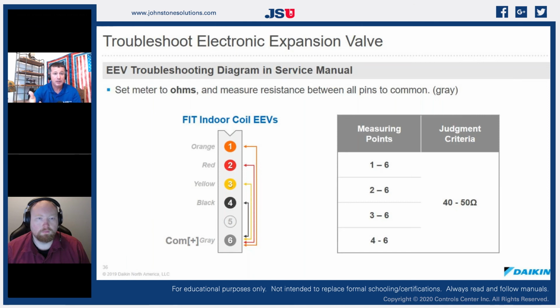When you fire up one of these units, you're going to hear that EEV opening and closing, and that's all it's doing, it's just firing at those individual windings, trying to open that thing up. Moving some of these expansion valves will run a couple thousand steps in 1/8 of an inch. That's a lot. All it takes is for one of those windings to be out, and that thing is not going to open and close properly.